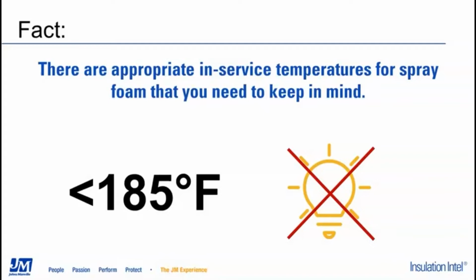A common application where this comes up is a boiler that sits outside of a hospital, for example, and they want to insulate those pipes, or what they call trench foam, on the pipes running from the boiler into the hospital. Obviously, by virtue of the fact it's a boiler, the steam through those pipes is over 212. So that's just one area to be careful with.